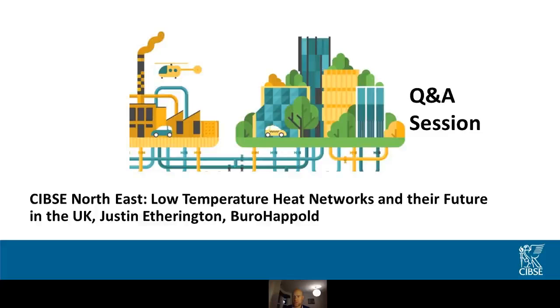In terms of what happens in future for a DN300 pipe reaching the end of its lifetime - like any asset, there needs to be a managed replacement strategy. That could mean sectional replacement with temporary heat supplies for impacted elements. Most heat network designs have a contingency solution allowing an alternative heat source at point of use. You need to consider replacement as with any asset - pipes are a lot less flexible to replace than cables, but we have similar issues with strategic water mains. It's really about managed replacement, but I think not enough consideration is given to long-term future replacement.